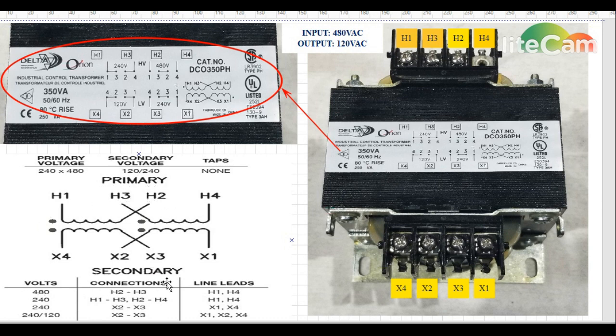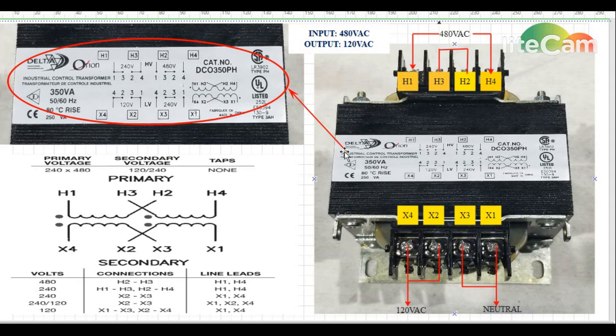And the secondary coil is the coil where we get the desired output, whatever we want. For this video our output will be 120 AC. So these terminals X4, X2, X3, X1 represent our secondary terminals, and we will be getting a 110 as output from these terminals. So let's have a look at the wiring drawing on the transformer. So this is the wiring drawing on the transformer.